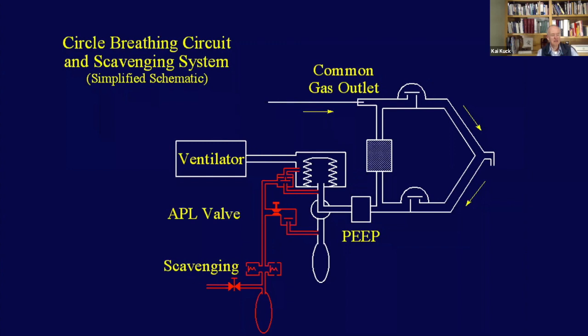What else do I have on my list here? Yeah, so here's another one. In an ICU ventilator, if something goes wrong with all these sophisticated ventilation modes, these ICU ventilators automatically switch back to mechanically controlled ventilation, just to at least make sure that the patient gets ventilated. Anesthesia machines, if something goes wrong, just turn off. Well, the machine doesn't turn off, but the ventilation turns off, and they go into what they maybe a little bit euphemistically call a spontaneous or manual mode. In other words, if the patient doesn't breathe on their own, or if you're not there to squeeze the bag, because this is ICU ventilation, maybe you're not sitting next to it.